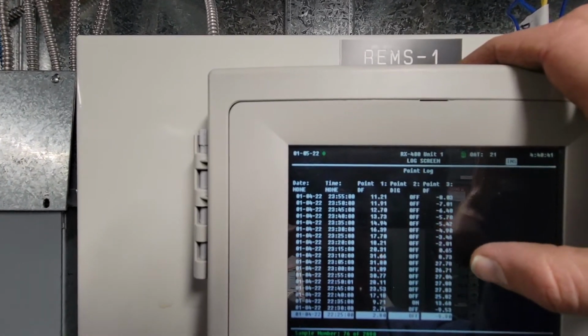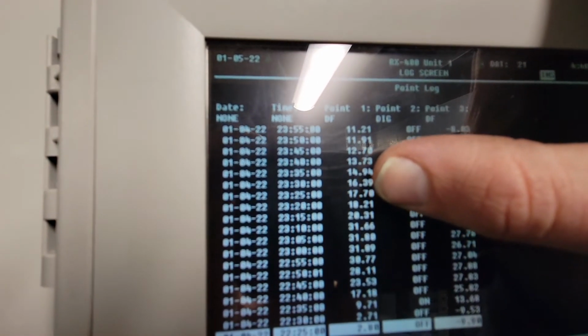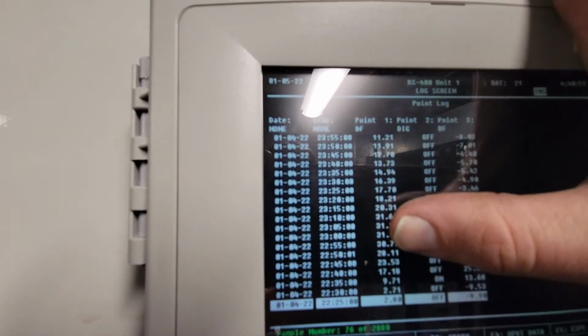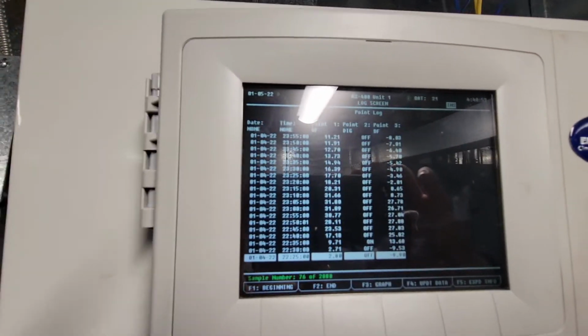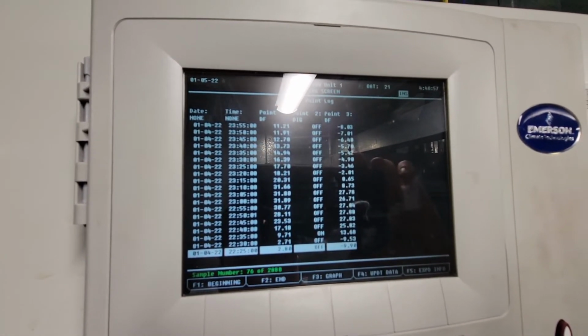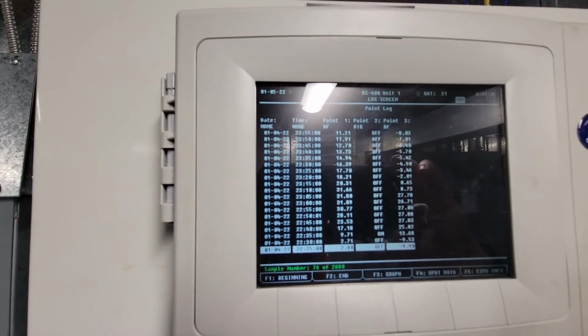And you can see that as this goes on, this is down almost immediately, right? This goes down to -2. This side is 18, 17, so this side is taking way longer. So we can see that temperature probe number 2 is having issues with those case temps coming down after defrost. And we can use this logarithmic comparison to do that.